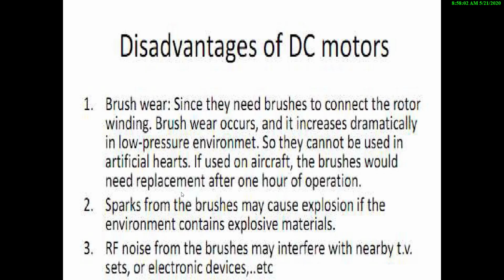And the disadvantage of a DC motor is brush wear. Since they need brushes to connect the rotor winding, brush wear occurs and it increases dramatically in low pressure environments, which is common in aircraft. The brushes would need a replacement after 1 hour of operation. Therefore, the brushes are the main drawback of our DC motor, and sparks from brushes may cause an explosion if the environment contains explosive material. And the third one is RF noise from the brushes, which may interfere with nearby TV or other electronic devices.